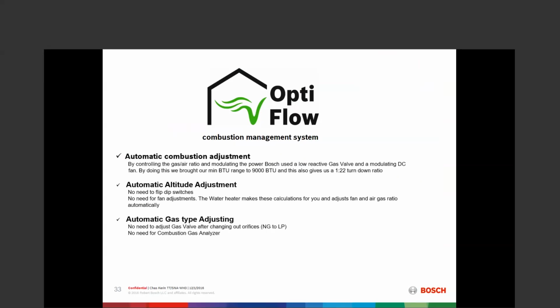In converting it, we are going to put in a set of orifices, and then through the HMI, through the display, tell the OptiFlow that it is now an LP unit. Beyond that, the unit is able to set itself up for LP. We do not need a flue gas analyzer in order to convert this to LP.